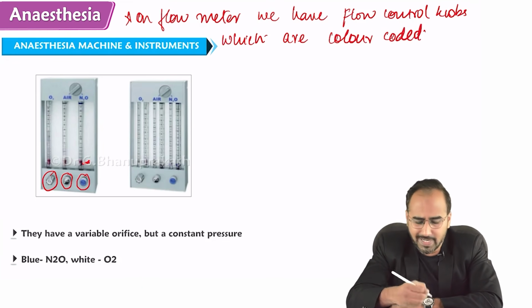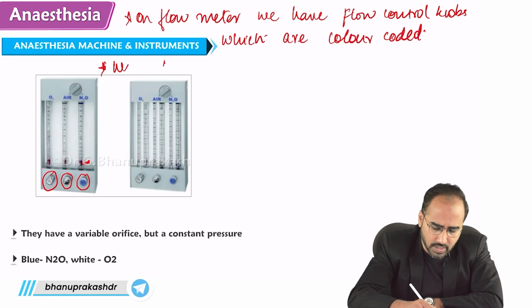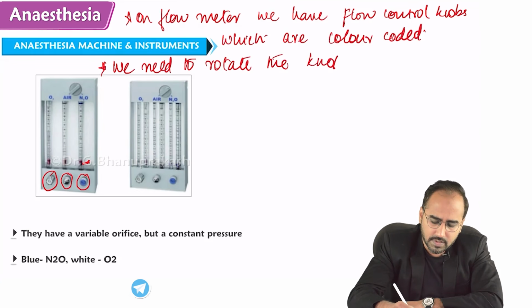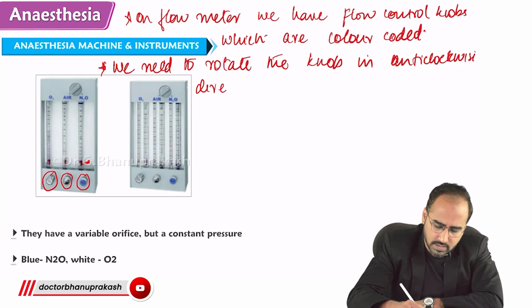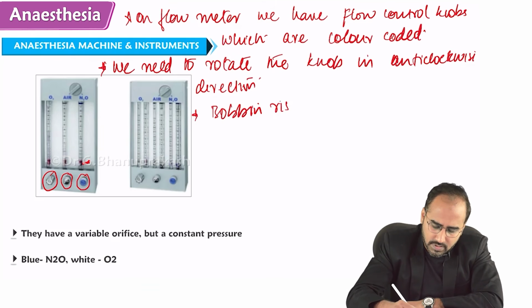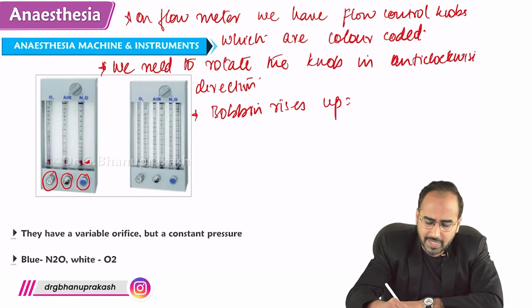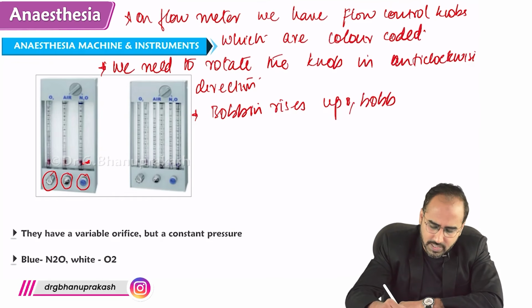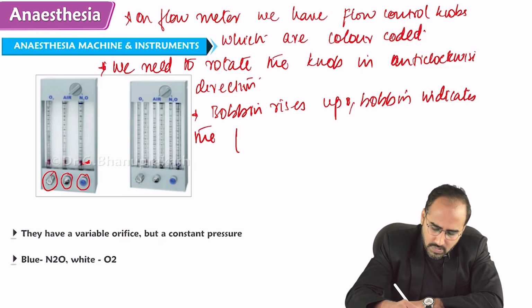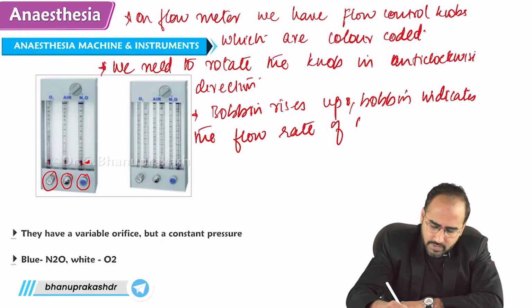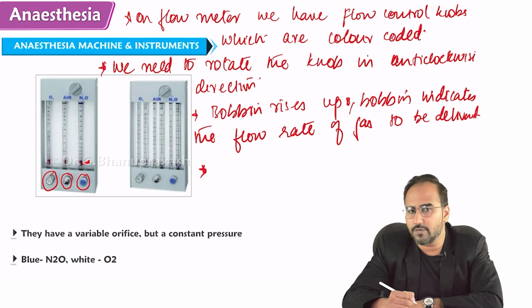Okay? If you want to turn on the flow meter, what we need to do? We need to rotate the knob in anti-clockwise direction. And what happens? The bobbin rises up. What does bobbin indicate? Bobbin is a small structure guys. Bobbin indicates the flow rate of the gas to be delivered. The bobbin indicates the flow rate of the gas to be delivered.